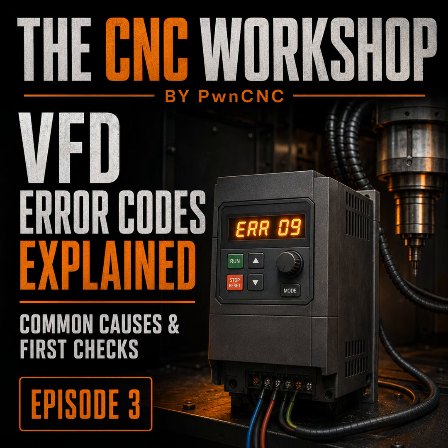What should someone inspect for ERR12 after everything is safely powered down? Inspect the entire spindle cable, especially where it enters and leaves the drag chain. Look for tight bends, pinch points, abrasion, crushing, or strain. Check the spindle side connector and the VFD side connector. If you are qualified to inspect the internal connections, look for loose output terminals and confirm the ground and shield connections are correct. And if it only faults when the machine moves, do not begin by rewriting every parameter in the VFD. Correct. Follow the physical clue first. Random parameter changes can add a new problem on top of the original one.